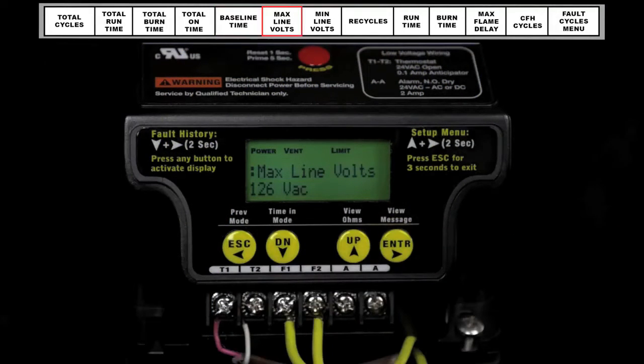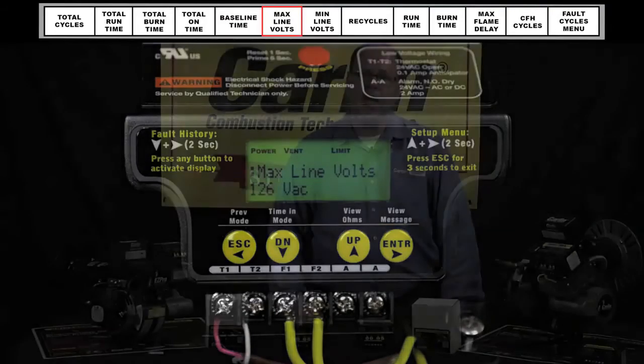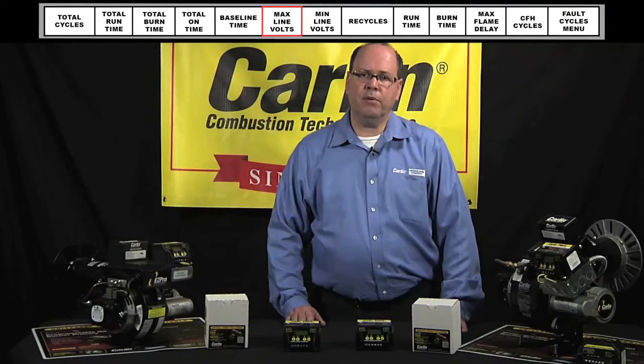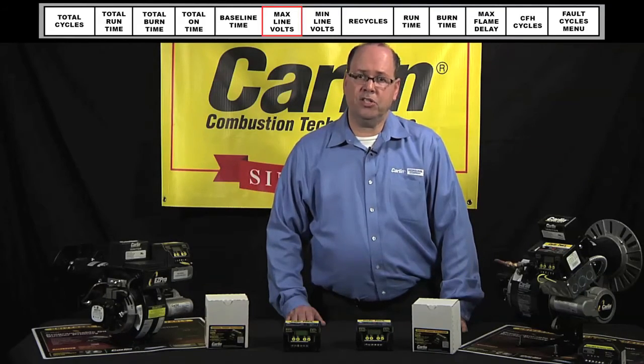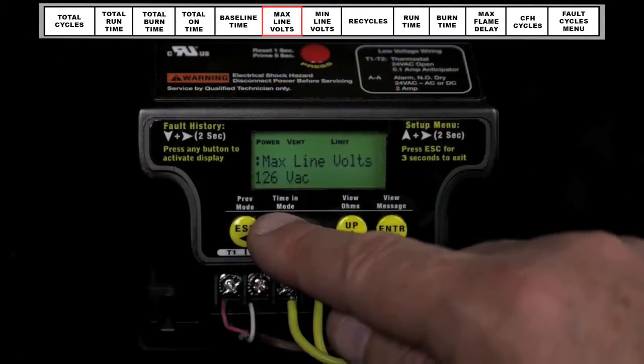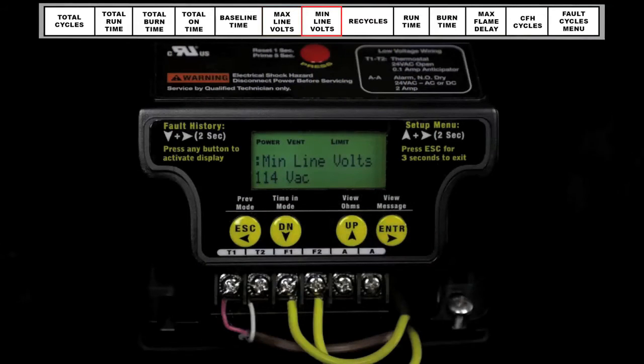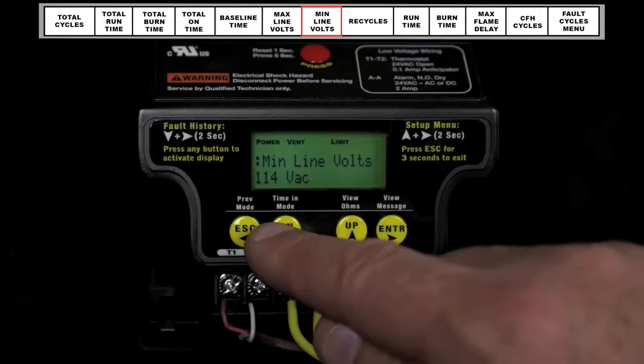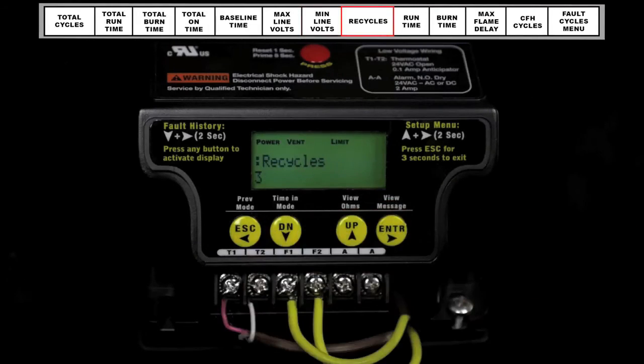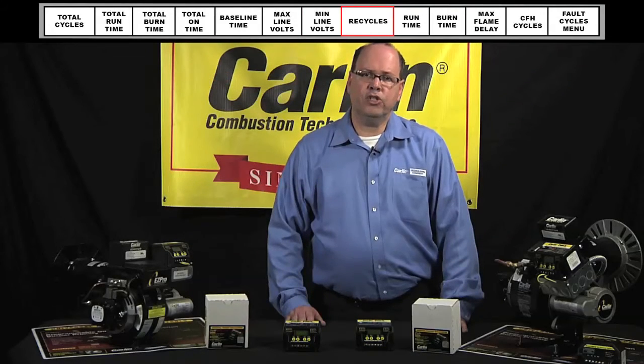Max line volts. The ProX is constantly monitoring the incoming voltage. Maximum voltage is recorded and displayed here. Let's press down again to get minimum line voltage. Minimum voltage is also recorded and displayed here. Go into the next option now, recycles. If the recycle feature has been turned on, then total recycles will display.